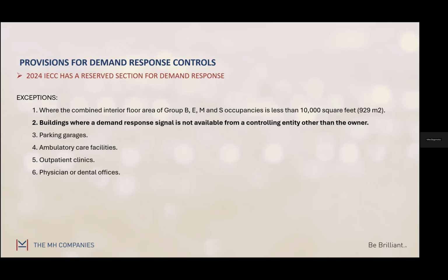And then parking, I'm not really sure why parking garages were added on there. Maybe that's for safety and security purposes. Although, reducing your lighting by 20% doesn't have a very huge impact on the overall lighting output. So maybe they're concerned that in maximal lighting calculations, there's going to be some dark corner in the parking garage, and if you reduce it by 20%, that might endanger someone. So that's my 2 cents there. But that's demand response.